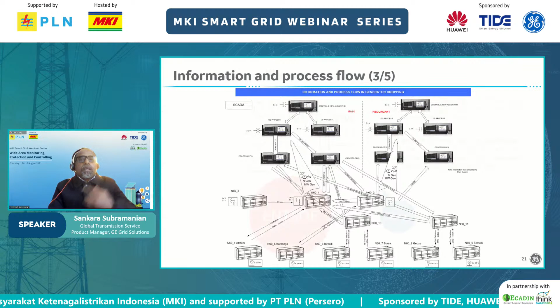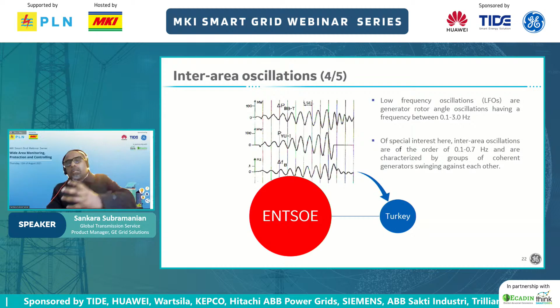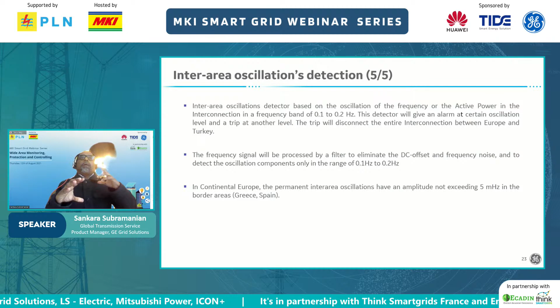Very critically, inter-area oscillations are a special thing to be dealt with in this case, because ENTSO-E being a larger system and Turkey being the smaller system, we had to deal with oscillation detectors. These were developed way back in 2010 to be employed along with the load shedding and generator dropping schemes.